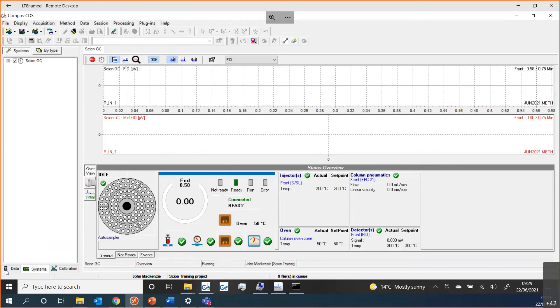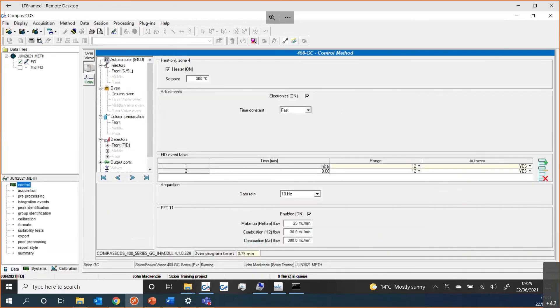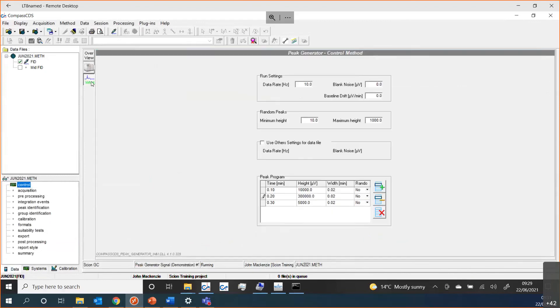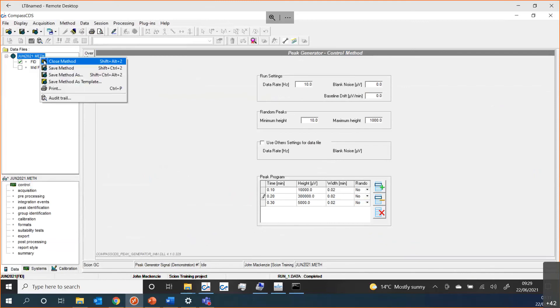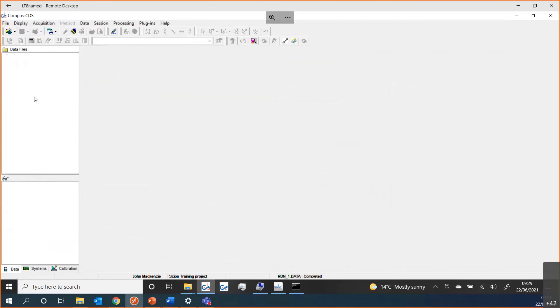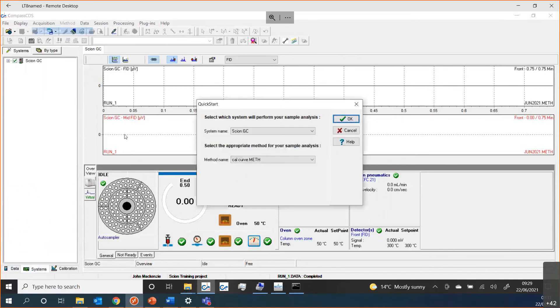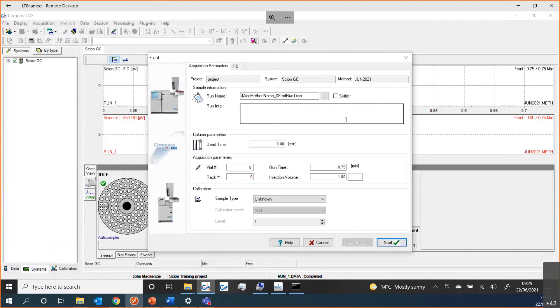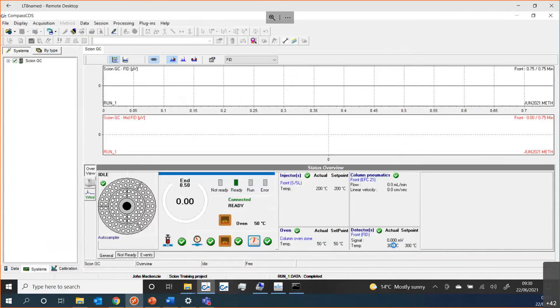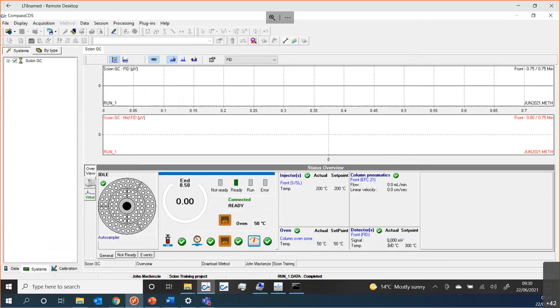Let's go back to our method. I did think we had created all the sections that we needed. Did we do a save? Let's just close the method to be sure. Still no data. My run is finished. Let me try just a quick one again, just to confirm it's definitely broken and not going to work for me. There we go. That's looking much better. And start. Yes, I suspect in my case to get through this, that I forgot to press the save button. And of course, it didn't update the changes into my method until I pressed the save button.